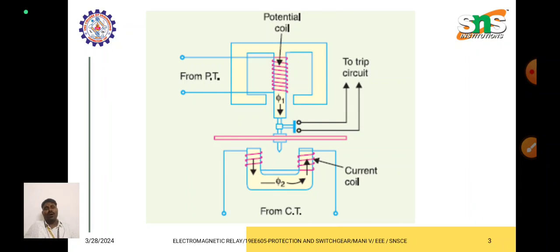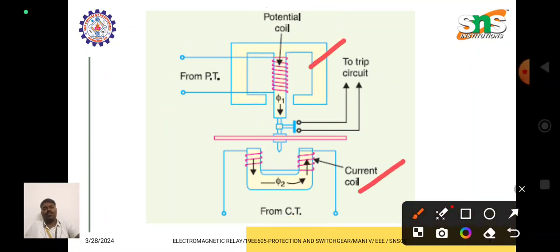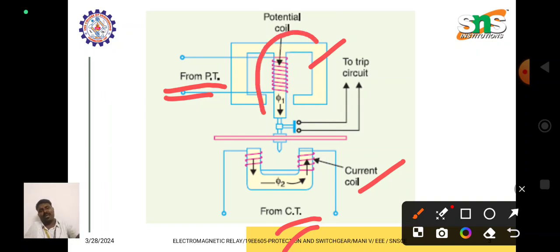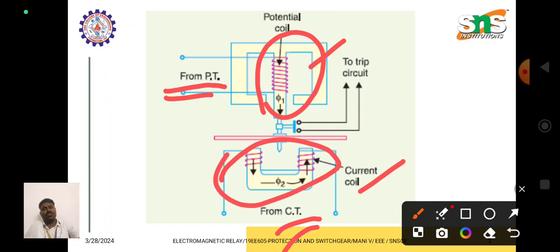Here it contains two electromagnets, one is the upper electromagnet and the second one is the lower electromagnet. The upper electromagnet carries a coil, and we get the power supply from the potential transformer, that is, the voltage supply. For the lower electromagnet, we get the power supply from the current transformer, that is, the current. The upper electromagnet is from the potential transformer and the lower electromagnet is from the current transformer. Each carries a coil. In between the upper and lower electromagnets is an aluminum disc, which is free to rotate because of its low weight.